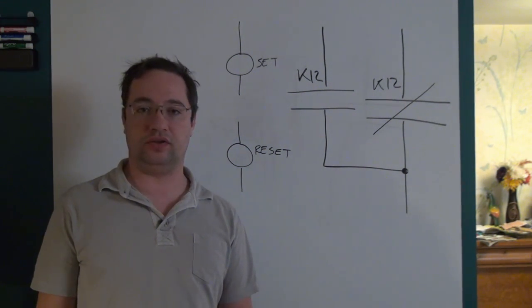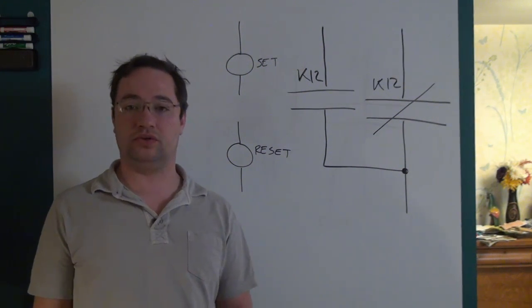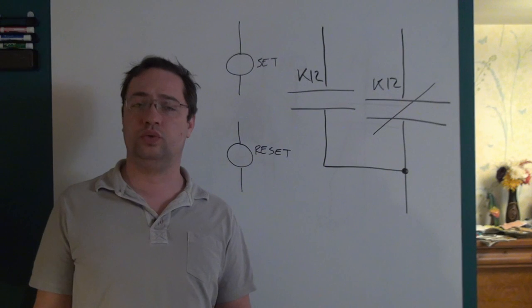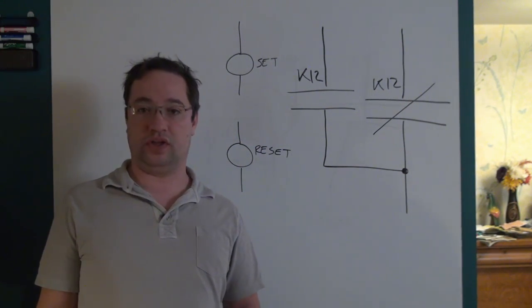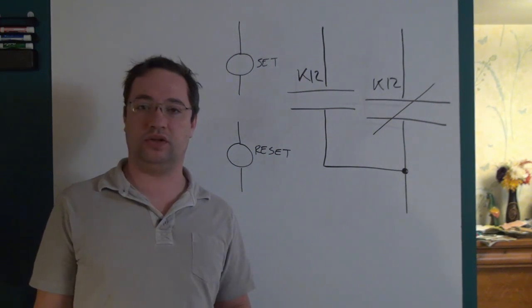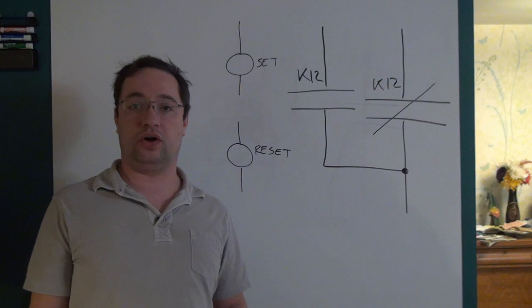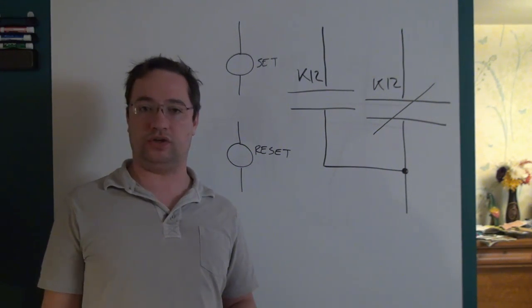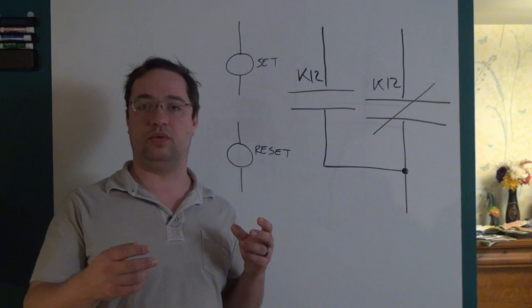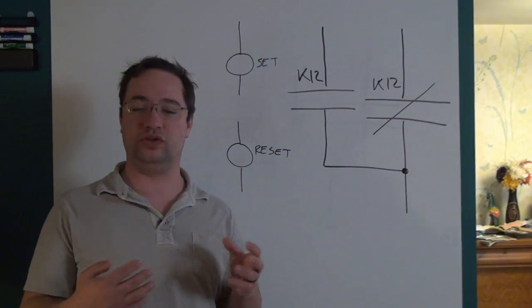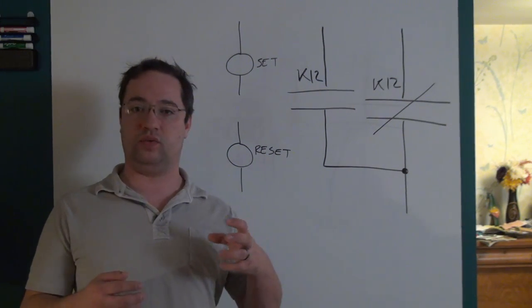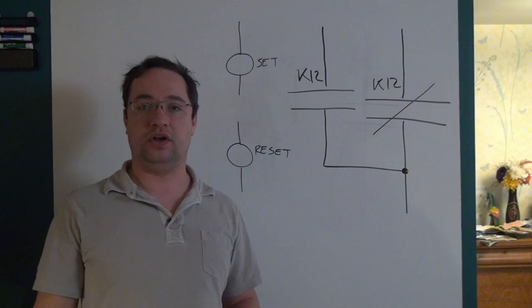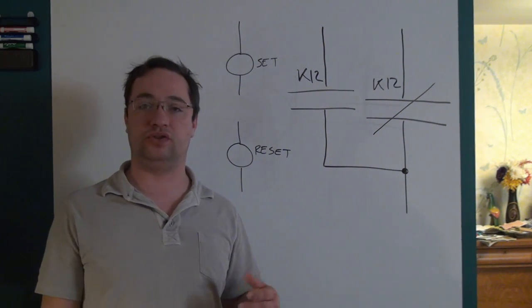Another relay variant is a force guided relay, probably the most confusing to understand. A force guided relay always has two or more poles, and the multiple poles are mechanically attached to each other such that if one fails to switch properly, the rest will also not switch. You never get the instance of one pole stuck while the rest switch off. This is generally used in safety-type circuits.